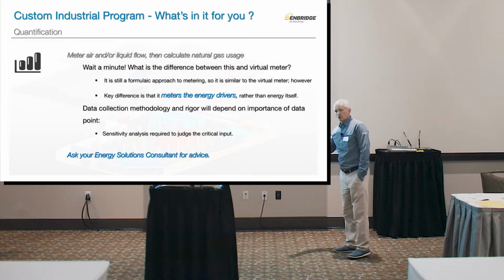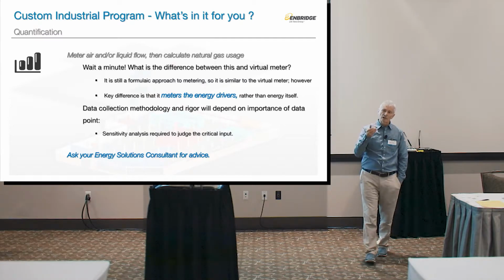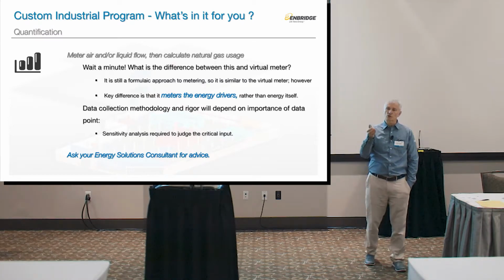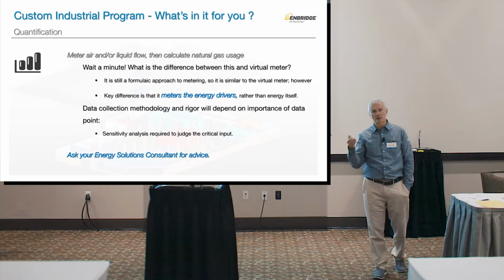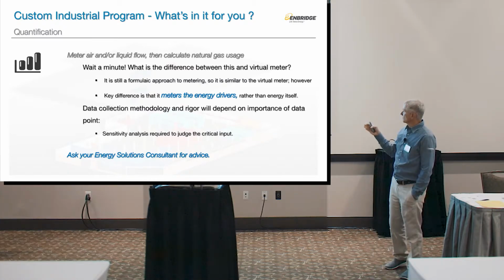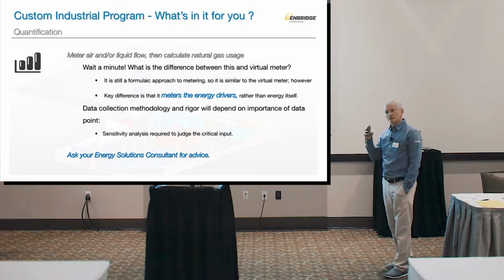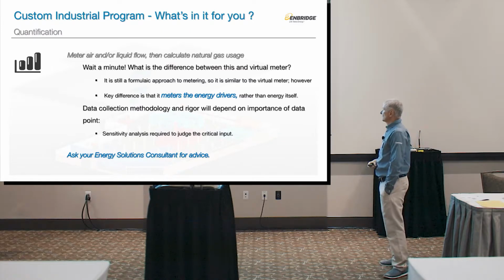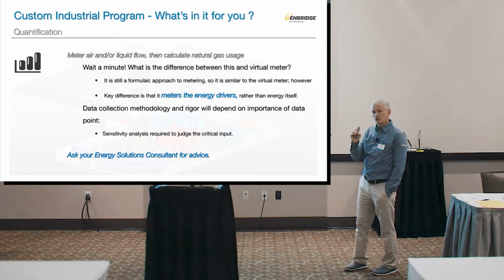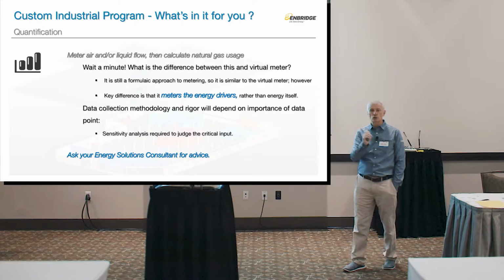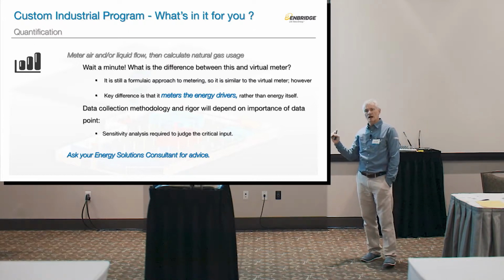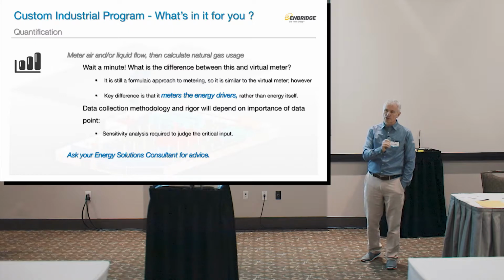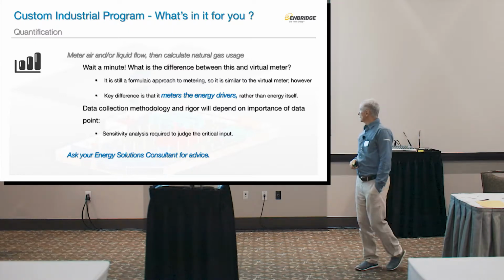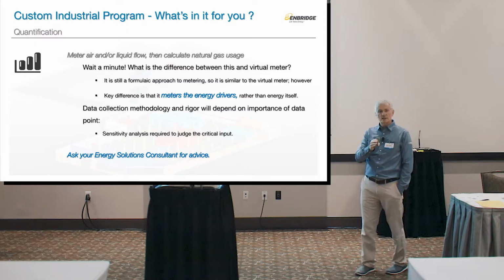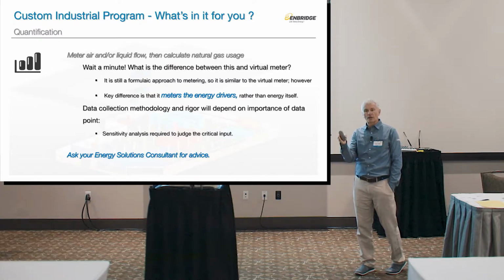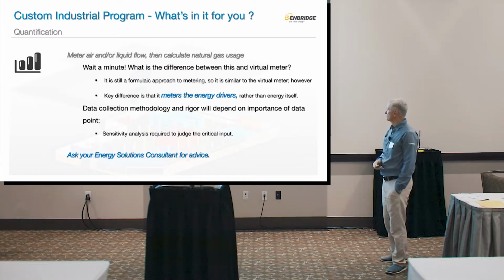Then the next methodology is very important for us: measuring other sources of information, confirming input assumptions rather than metering natural gas. And a lot of people will say, well, that's like a virtual meter. But the key difference is that now we are measuring the energy driver. We do not try to virtually meter or meter actual energy. We're metering the energy driver, what drives that energy. So usually it ends up being you either meter air or liquid, because those are the two things that you heat.